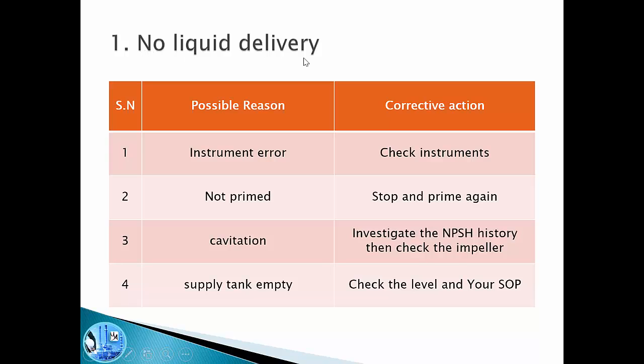The first problem is no liquid delivery. What could be the reason? The first reason could be an instrument error — our flow meter is giving misleading information and we need to recheck it. Maybe the pump is not primed, so we have to stop and prime again. Maybe cavitation is taking place and we need to investigate the causes. Maybe there is low net positive suction head delivered, and we need to check the impeller mechanically. Maybe the supply tank is empty — we should check the level physically, calibrate the related instrument, or review the standard operating procedure to ensure proper tank level before starting the pump.